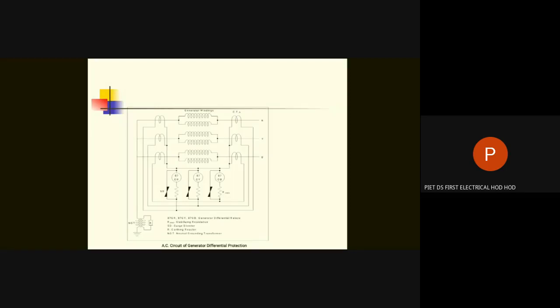You can see that the neutral of the generator is connected through a neutral grounding transformer to a reactor. That reactor is of 1 ohm, and that 1 ohm, when reflected to the primary of the NGT, neutral grounding transformer, is of the order of some 4000 ohms. And this value, 4000 ohms, will restrict the earth fault current to a value of 2 ampere, as we were discussing. You cannot connect the reactor directly in series with the neutral point, because then 4000 ohms, such a large ohmic value, would not be feasible technically.